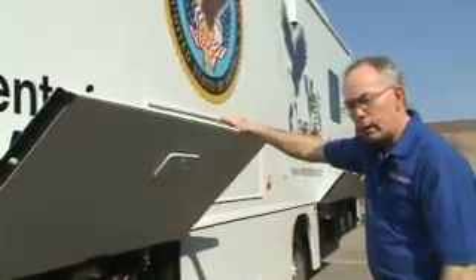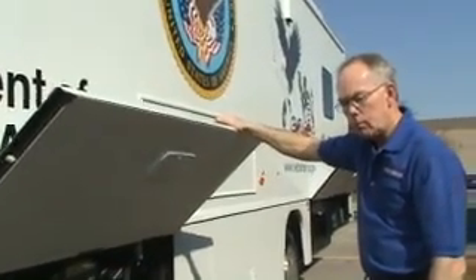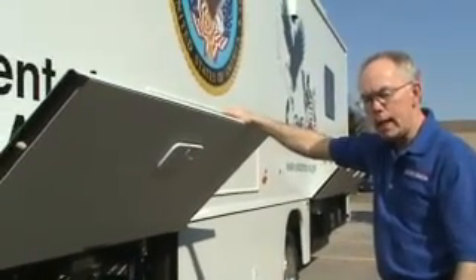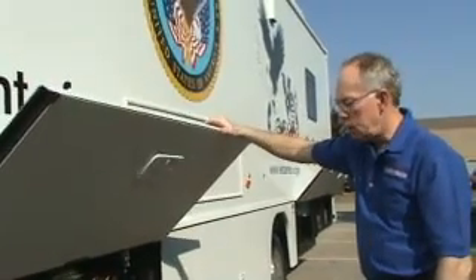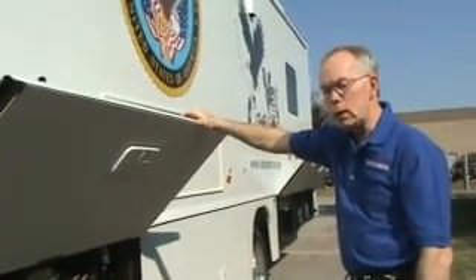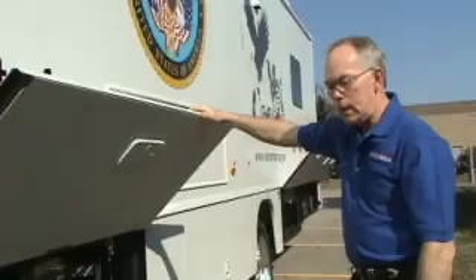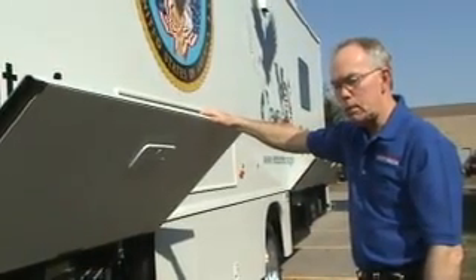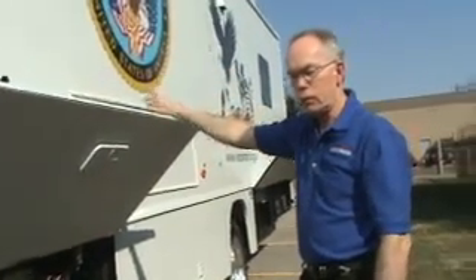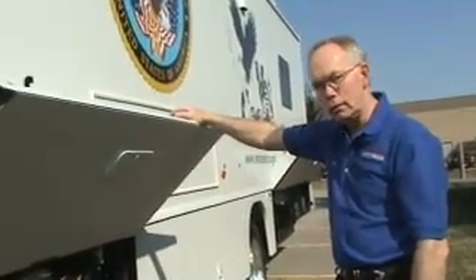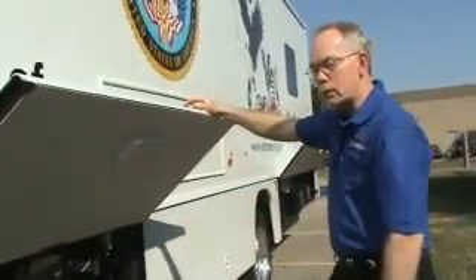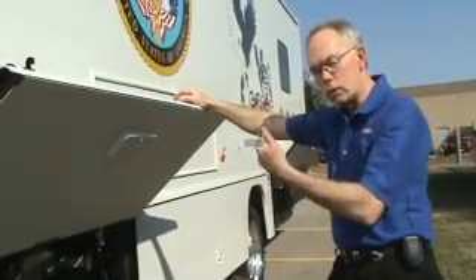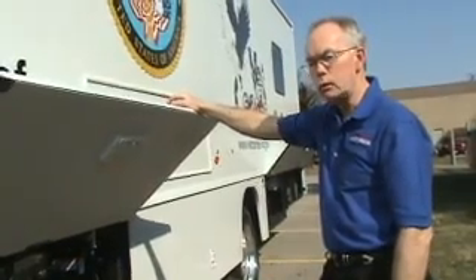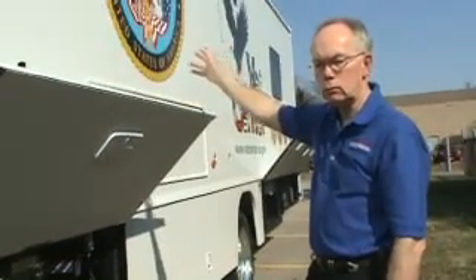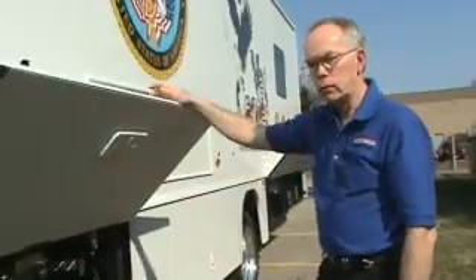There's a handout that I'm going to leave with all of the vehicles. On any mobile application that has a generator on board, you don't want to start or stop the generator when it's under load. What I mean is, in the summertime if you have all the air conditioners turned on, or in the winter all the heaters on, it's hard on the generator to try to start or stop while under load. So turn everything off in the panel, remove the load, and then go ahead and start or stop the generator.